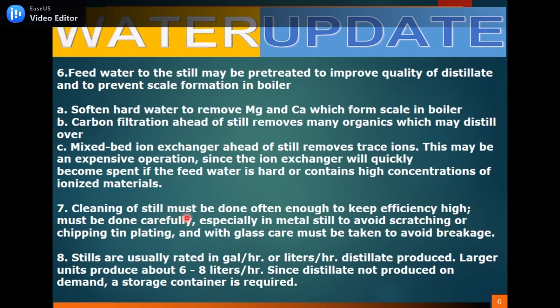Cleaning of the still must be done often enough to keep efficiency high. It must be done carefully — especially with metal stills — to avoid scratching or chipping the lining, and with glass stills, care must be taken to avoid breakage. Stills are usually rated in gallons per hour or liters per hour of distillate produced, with larger units producing about 6 to 8 liters per hour.